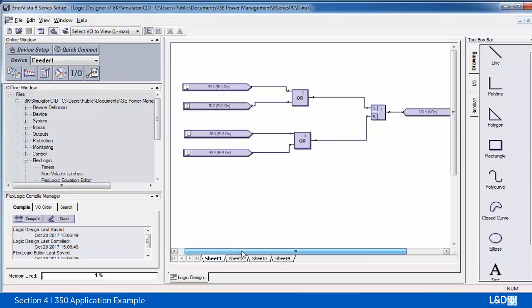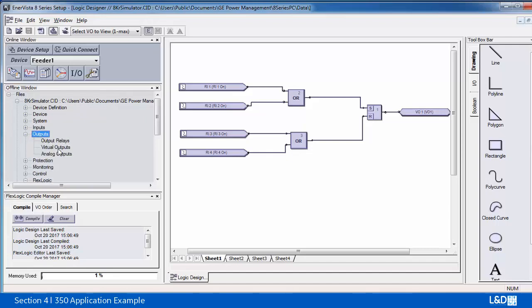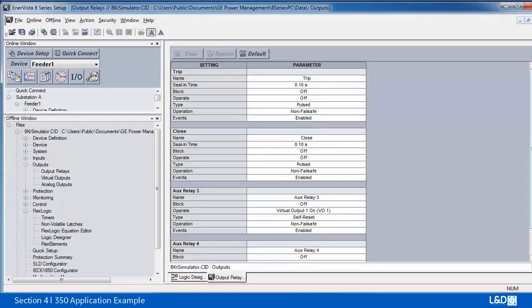So from here, remote inputs 1 and 2 are used to close the breaker. This is sent to the S of the latched gate via an OR gate. Then remote inputs 3 and 4 pass through an OR gate and are sent to the R of the latched gate. This will be assigned to virtual output 1, and virtual output 1 will be assigned to the output relay, so output relays 3 and 4.